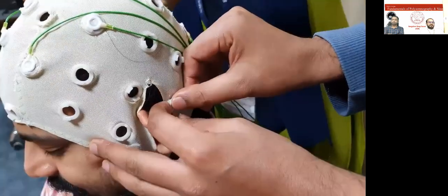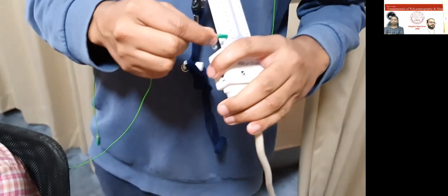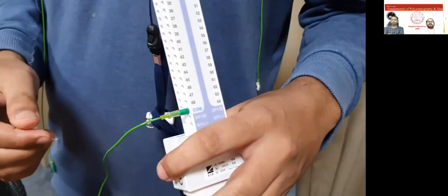You keep placing other electrodes as well. So as you can see, in some places, once the electrode is ready, you will be plugging in those electrodes directly to the amplifier. But we would highly recommend having something called a junction box. So junction box is more like an extension cord where you will have slots wherein you fill the electrodes, and it is detachable. And if the subject wants to go for a washroom break in between, we can just disconnect the junction box, and the subject can go to the washroom and come back.